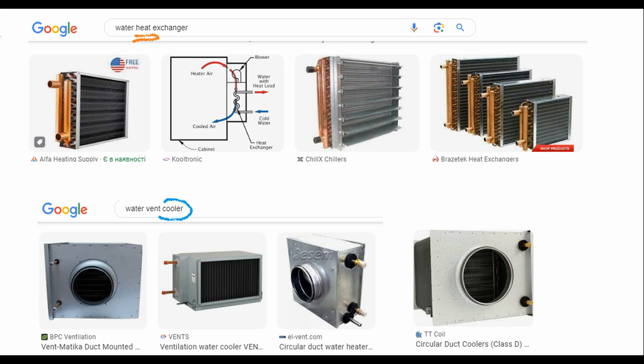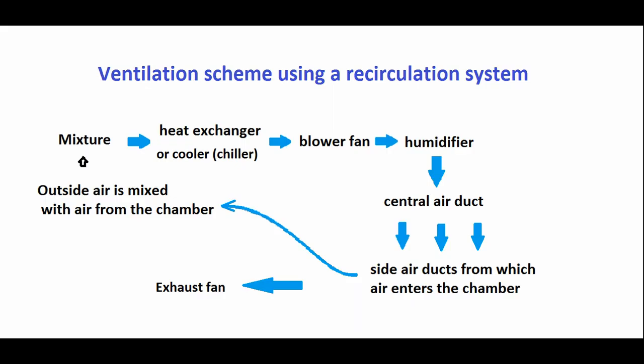We need a lot of air. If there are 10 tons of substrate in the growing chamber, we need to prepare 2,500 cubic meters of air every hour. It can be very expensive to warm or cool this amount of air — sometimes this is simply not possible as the equipment does not cope with such a task. But in the chamber we already have air that has the optimum temperature and, very importantly, the optimum humidity too. We can use it, and thus we will facilitate the task of preparing air for ourselves.